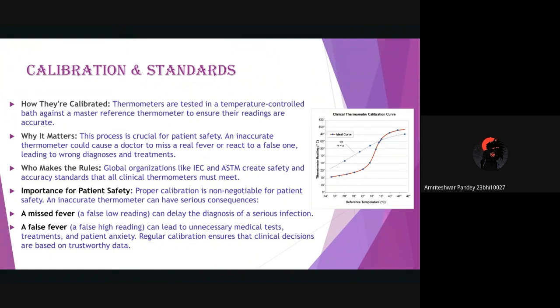Calibration and standards explains the process and critical importance of calibrating clinical thermometers. So first question is how they are calibrated. Thermometers are calibrated by testing them in a highly stable temperature controlled bath and comparing their reading to a master reference thermometer. Second question is why it matters. This process is crucial for patient safety. An inaccurate thermometer could cause a doctor to miss a real fever or react to a false one, leading to a wrong diagnosis and treatment. Next question that arises, who makes the rules? Global organizations like IEC and ASTM create safety and accuracy standards that all clinical thermometers must meet.